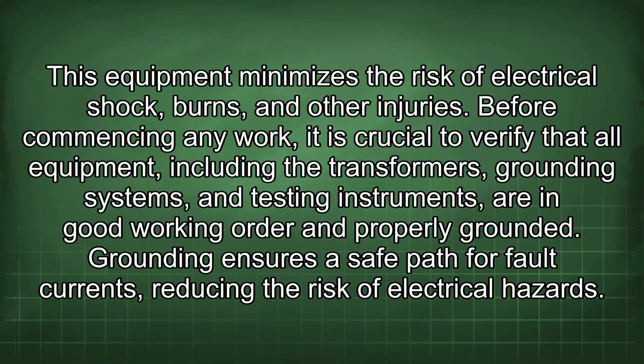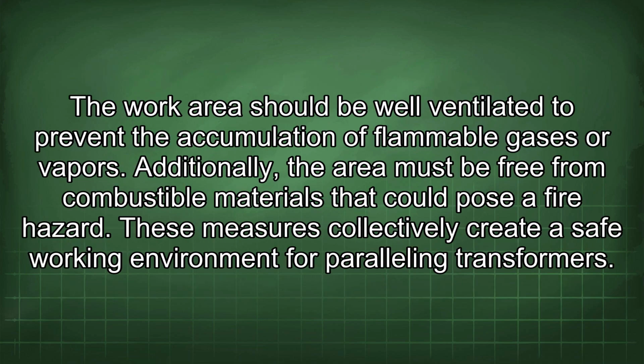Before commencing any work, it is crucial to verify that all equipment, including the transformers, grounding systems, and testing instruments, are in good working order and properly grounded. Grounding ensures a safe path for fault currents, reducing the risk of electrical hazards. The work area should be well ventilated to prevent the accumulation of flammable gases or vapors. Additionally, the area must be free from combustible materials that could pose a fire hazard. These measures collectively create a safe working environment for paralleling transformers.